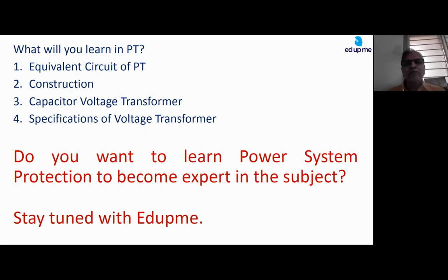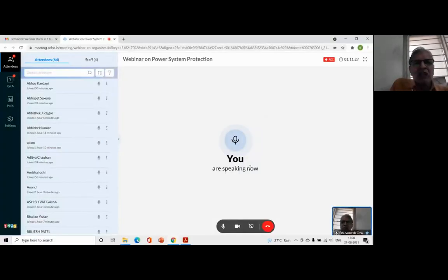Yes, please. There is another question. Reverse power for steam turbine and gas turbine, is there any difference in the setting? I think STG is more sensitive. Any reason? Steam turbine and a gas turbine, yes. Is there any different setting for the reverse power? True. Reversal of power in a steam turbine, reversal of power in a gas turbine, reversal of power when you are using a hydro turbine, they are all in a way different. And different settings are to be applied in this case.